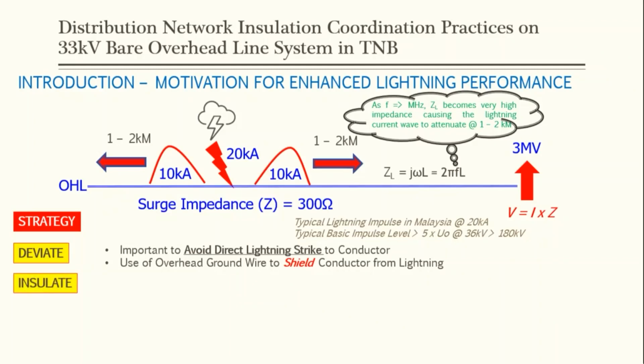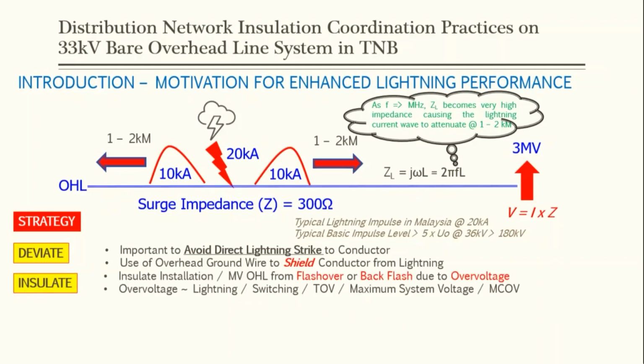We insulate. Why do we need to insulate? We insulate the installation of the medium voltage overhead line from flashover or back flashover due to overvoltage. And as I've said earlier, the overvoltage can be anything from lightning, switching, TOV, maximum system voltage, and of course we also need to consider the maximum continuous operating voltage when we want to insulate any electrical installation.